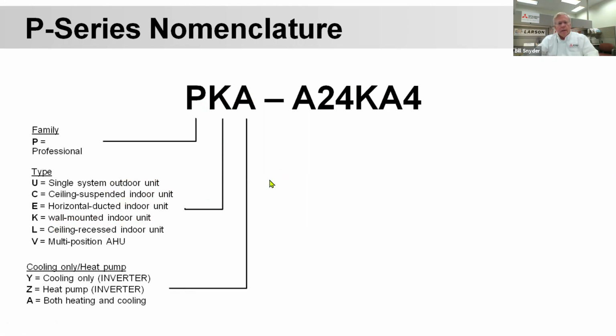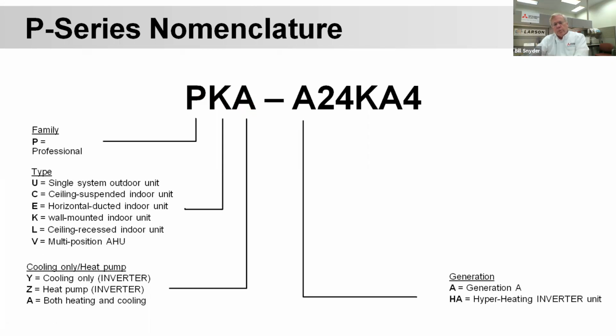The A indicates that it is available for both heating and cooling. So this wall unit, the PK wall unit, can be used for both heat pump and cooling only. The M series cannot. You have a separate cooling-only wall unit for Mitsubishi M series and a different one for the heat pump. But on the P series, they're available to use for both heating and cooling. And if this was a PUY, it would be cooling only, and a PUZ would be an outdoor heat pump. The next unit would be a generation change.